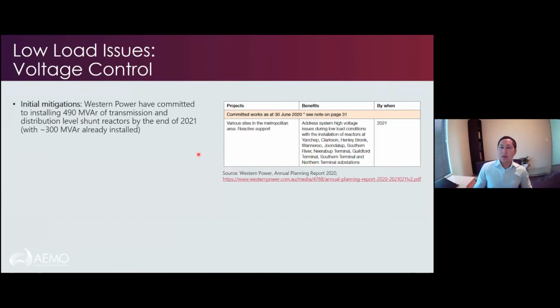However, Western Power have actually committed to installing quite a lot of shunt reactors in the system. They're committed to installing almost 500 MVars, with probably about 300 MVars already installed. And so right now, we don't have too much of a problem. At one point last year or the year before, we were having to switch out lightly loaded transmission lines that were injecting a lot of VARs. So now we're having to not do that as often. We'll see in September, October, but right now it's been pretty good. And with more transmission level shunt reactors coming in, that also improves the situation.